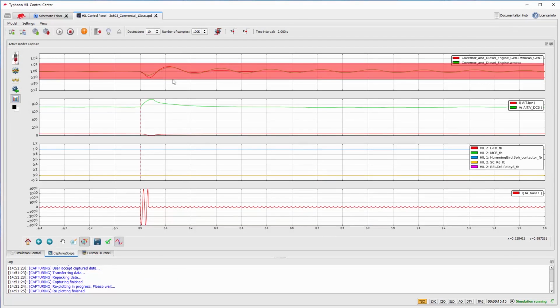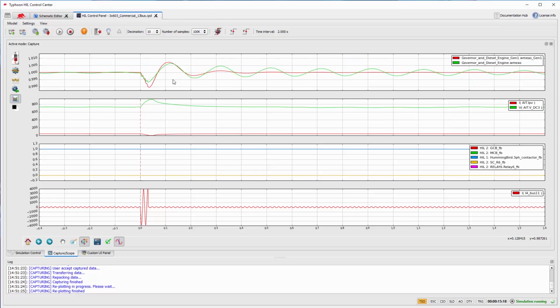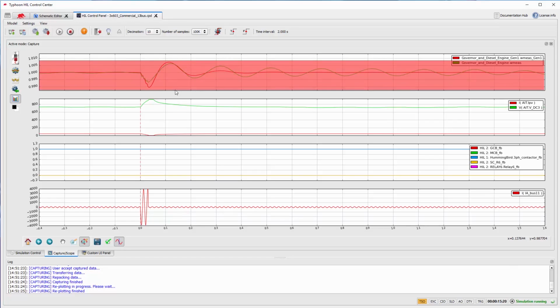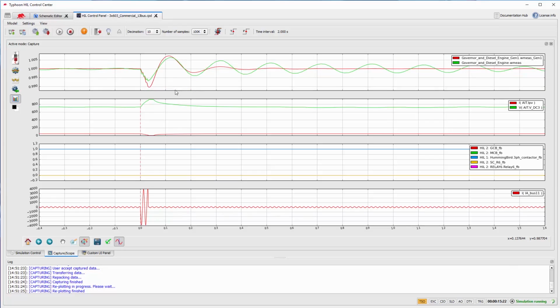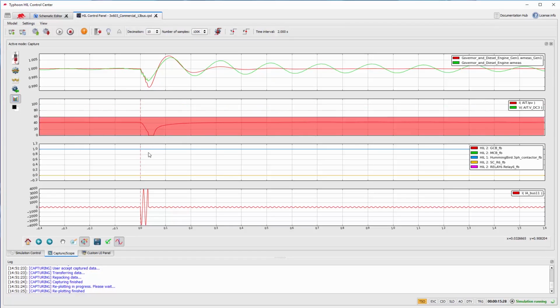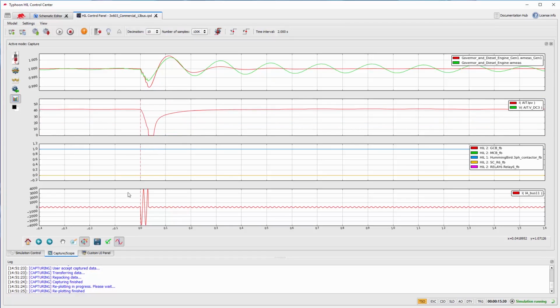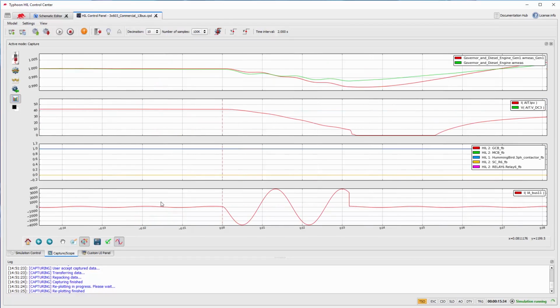This level of current is above the defined time over current limit, TOC, but smaller than the instantaneous over current limit. This means that the relay cannot open instantaneously, but with a time relative to the current level. For this case, the relay should only open if the fault stands more than 0.96 seconds. As this is not the case, the relay should remain closed. And that is what happened.